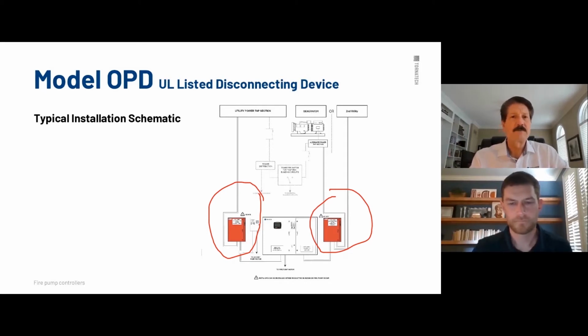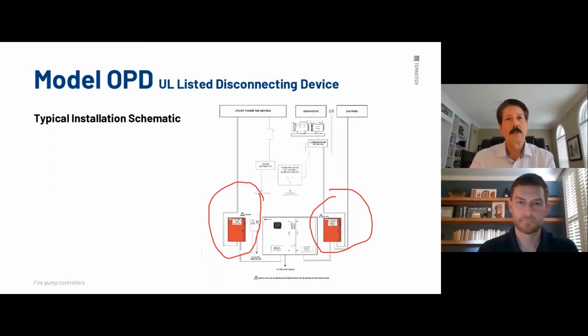And usually across the country, you've got varying levels of cost. It depends on what city you're in. You may find out that the cost to have this disconnected and reconnected by the utility is equal or more than what the cost of installing an OPD would be. And that's key, because once you have that main disconnect in there, it's there for life. You can open and close it anytime you want, whenever you need to. And the key issue here is like, okay, I don't have to deal with the utility. I don't have to pay the cost. Really what it does is it isolates the fire pump controller only. And when you deal with the utility having to shut down power, you shut power down to the whole facility. And what happens when you have a 24/7 operation, whether it's manufacturing, it's an airport, 7-Eleven, it's a hotel, where you have that activity going 24/7, you got to cut power totally. And it makes it very difficult when you're trying to run a business. So the investment and the value an OPD brings as a main disconnect is insurmountable.